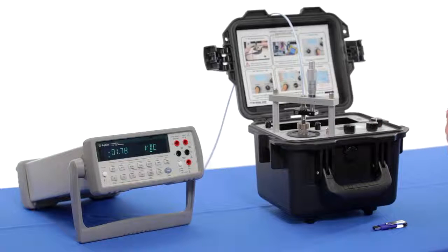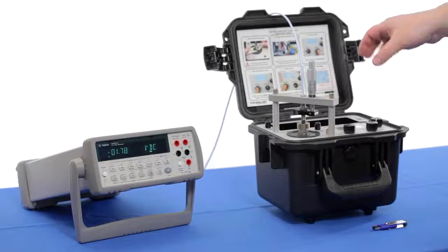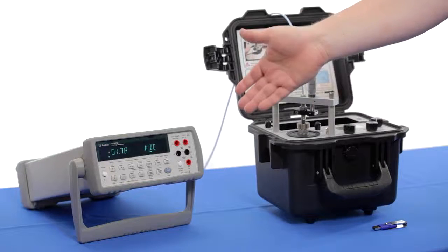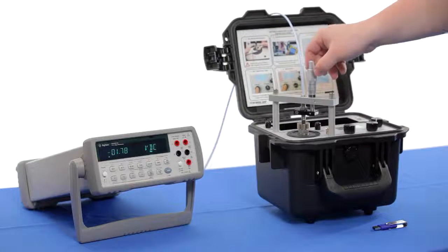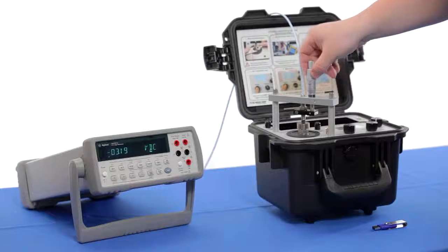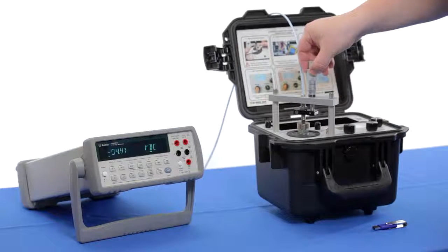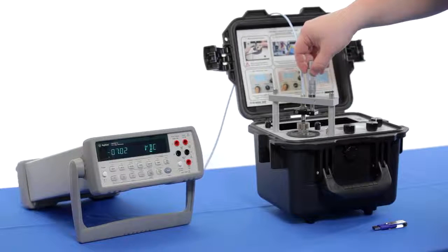The first step in performing a dynamic proximity probe calibration is to set the gap voltage and set the gap distance to 50 mils. So what I'm looking for on my voltmeter is -9 volts DC. So I'm going to turn my micrometer on my proximity probe adapter kit until I see -9 volts DC on the voltmeter. And this doesn't have to be the most precise measurement unless you're planning to shake the target at 40 mils peak or 80 mils peak to peak and use the proximity probe at its full range. But for good practice, we want to put it at 50 mils, which is the exact center of the proximity probe's dynamic range.